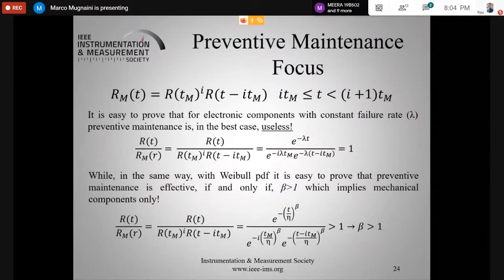So performing preventive maintenance on electronic components is barely useless, and you can even cause damage, because every time you assemble or disassemble electronics, you risk making a mistake. Instead, preventive maintenance on mechanical components has a benefit, because it can be proven that this ratio is advantageous if the failure rate is described by a Weibull probability density function where beta is greater than one.